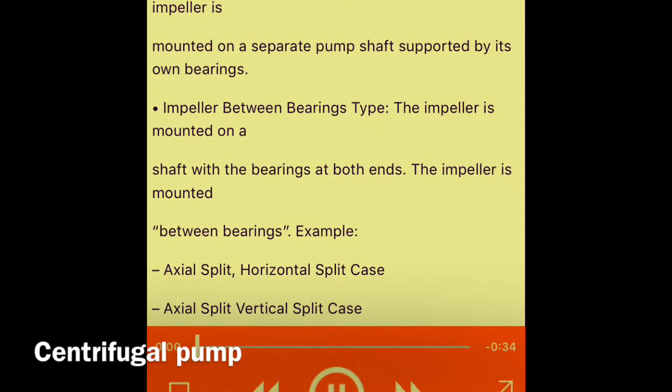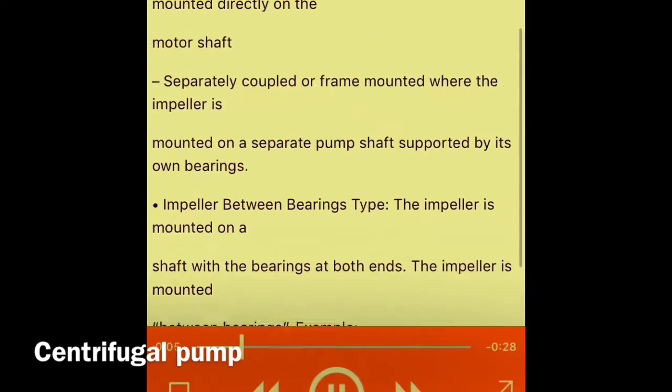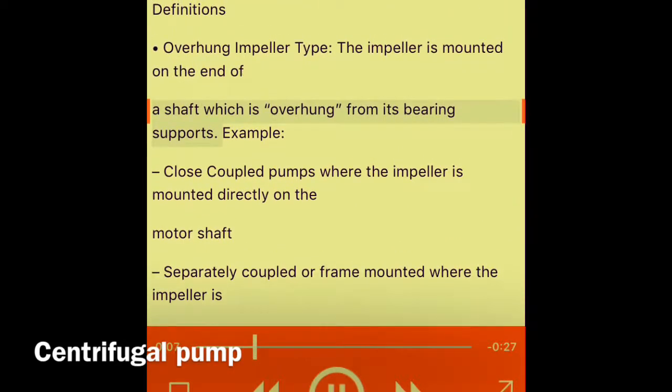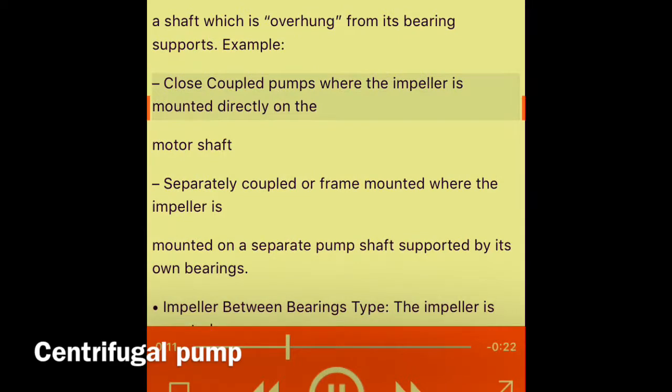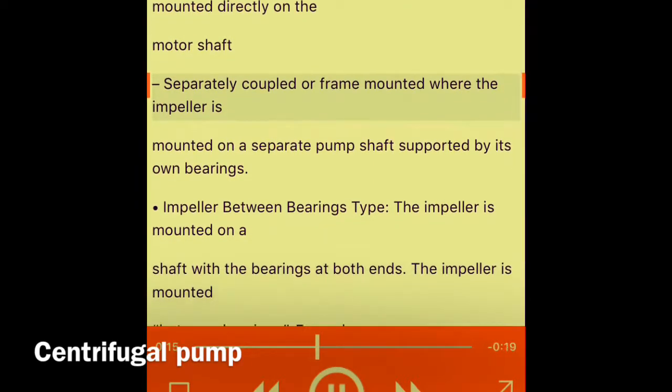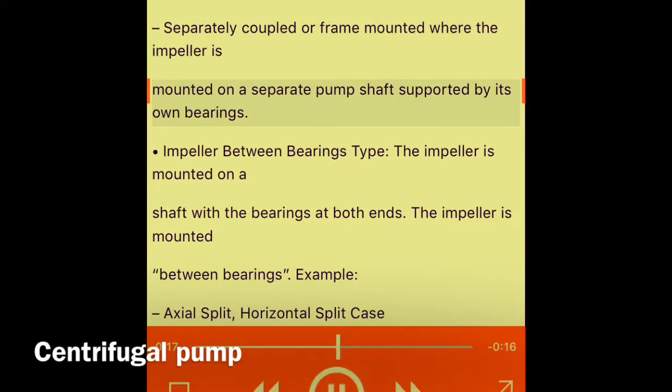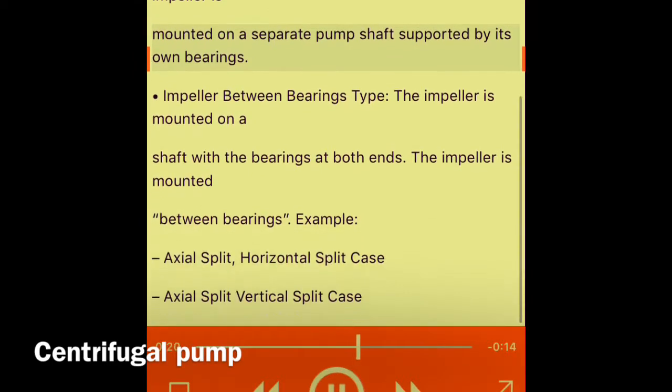Overhung impeller type: The impeller is mounted on the end of a shaft which is overhung from its bearing supports. Examples include close-coupled pumps where the impeller is mounted directly on the motor shaft, and separately coupled or frame-mounted where the impeller is mounted on a separate pump shaft supported by its own bearings.